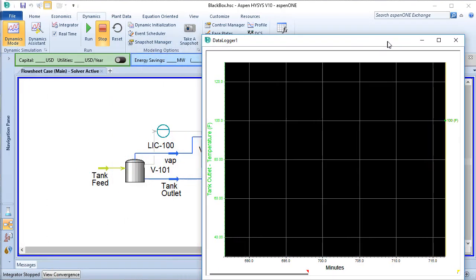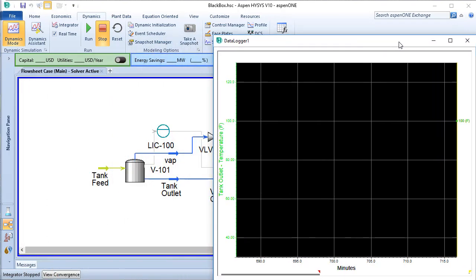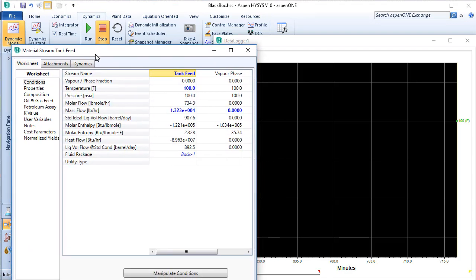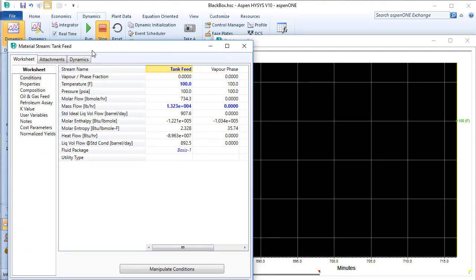A strip chart is pre-configured to plot the inlet and outlet water temperature. I know that each degree of temperature increase in the feed will cause the outlet temperature to increase by 1 degree, so the process gain is 1 over 1, or 1.